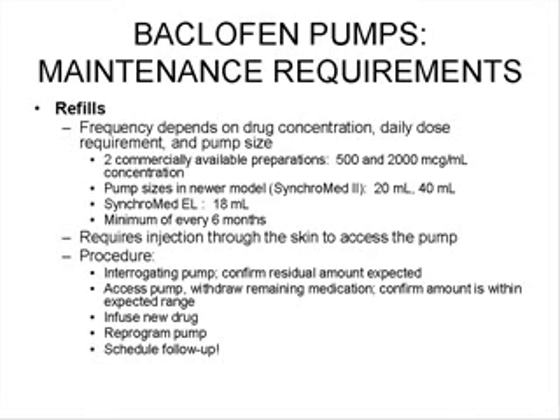So what does it take to maintain a pump? Because we have different phases, and I think people tend to worry the most about the actual implantation. And really what I want them to worry about beyond the implantation is what it's going to take to maintain this pump. And so let's talk about what it requires. So first of all, the most important thing are the refills. And really what it boils down to is the frequency of the refills will depend on which drug concentration is used and the daily dose that's required and the pump size. So it's equivalent to sort of gas in your car. You can only have so much in the system. It needs to be refilled periodically, and how much it needs to be refilled just depends on your use.